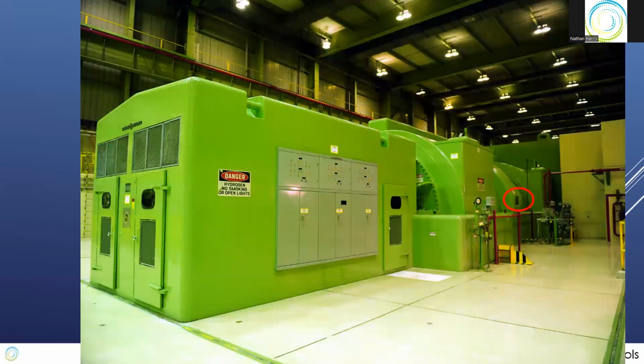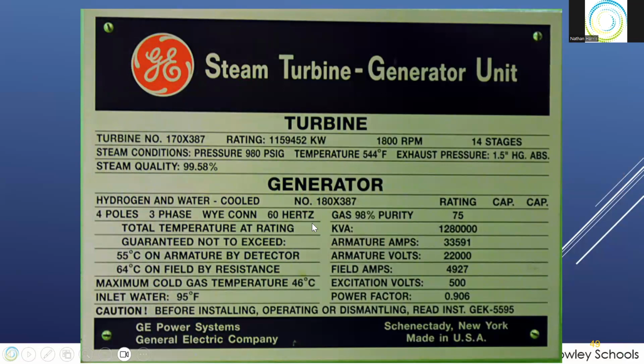And here's the next step on the other side. This is a big nuclear plant, and I think this is Nuki. Yeah, I think it is. But it's a large one. So here's your steam turbine back here, and here's your generator. These are the doors you walk in to look at the generator windings. Here's your exciter panel on the outside of it. There's a nameplate back here. We'll zoom in and take a look at that nameplate. And it's a gasser, right? So it's a hydrogen and water cooled generator. They have a water to air exchanger in there to keep it cool.